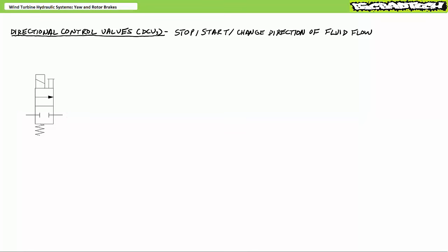A position performs a particular function. This is a closed position that does not allow fluid flow from left to right. This is a straight-through position and does allow fluid flow from left to right. This is a two-position valve. Most valves have a natural resting state asserted by some accessory device like a spring offsetting it to one side or a pair of springs centering a three-position valve. This particular valve is spring offset to the closed position such that flow from left to right is blocked. One might consider this valve normally closed.